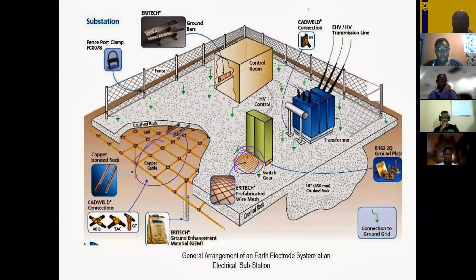So in terms of the resistance values we have to consider, for residential we can deal with 25 ohms. This is usually easily achieved by just driving a rod. So you have your 6 foot or your 4 foot rod, you drive them, put on your nut and make sure it is tight enough, and you're good.